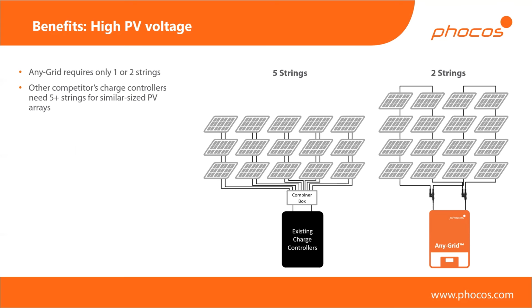And then also, you will need string fuses or diodes because there could be a reverse current situation between various strings. Virtually all the crystalline PV modules I know will accept up to 2 strings without any of these measures. So that really is one of the main ways you can save money with the AnyGrid, by saving on the number of strings you have, reducing those 5+ strings down to 1 or 2. And if you do that, you will just need standard Y cables if you're using 2 strings, and that's it. You don't need a combiner box, you don't need string fuses, you don't need string diodes and all those other things, which tend to add quite a lot to the system cost.